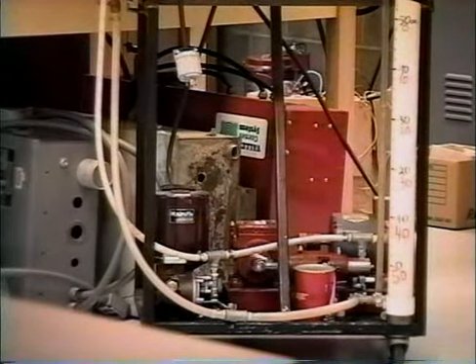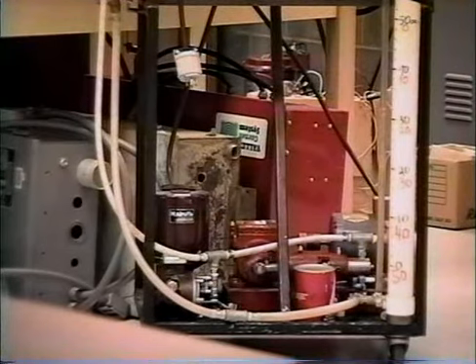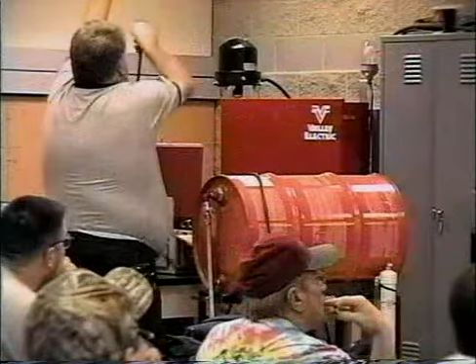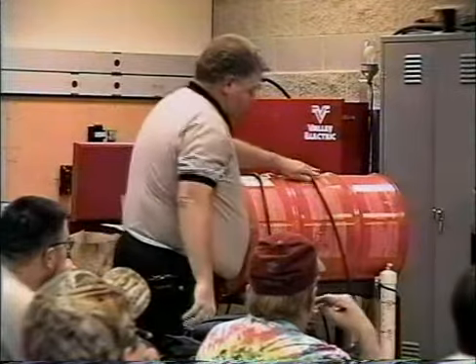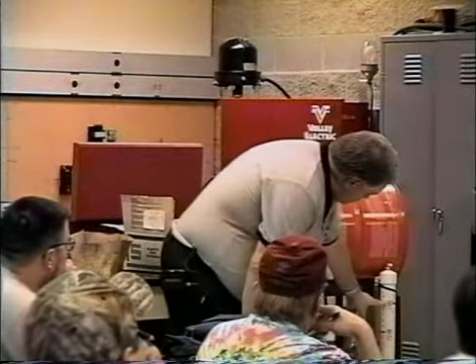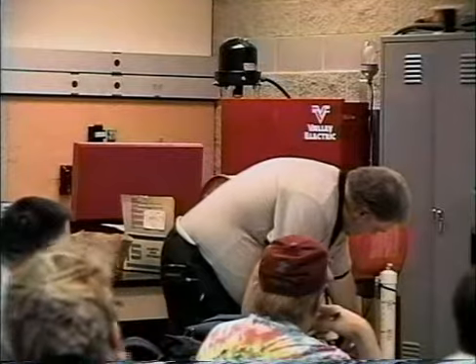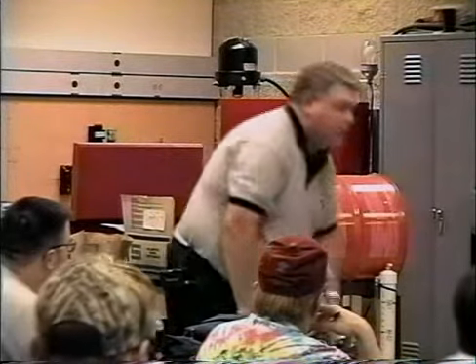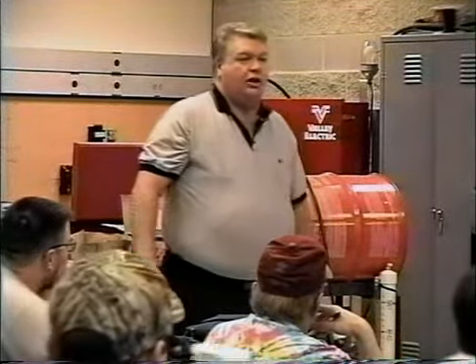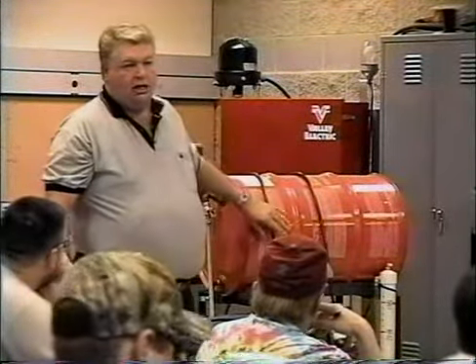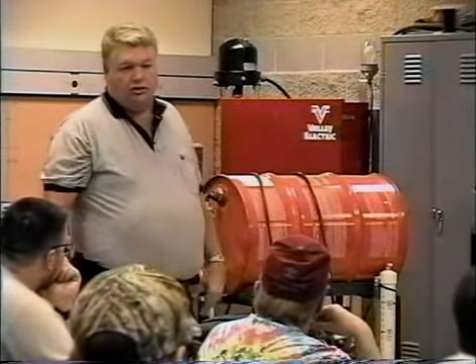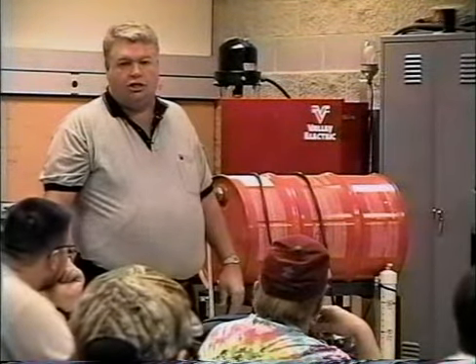One way I can do this is I'll just shut her down when we get to — that's about a minute, right about now. And now we can just read and see — I was reading it from the red zero down — and we've got about 19 and a half ounces that we've pumped out of there in a minute. So that gives us our calibration at the point that we're operating it at right now.